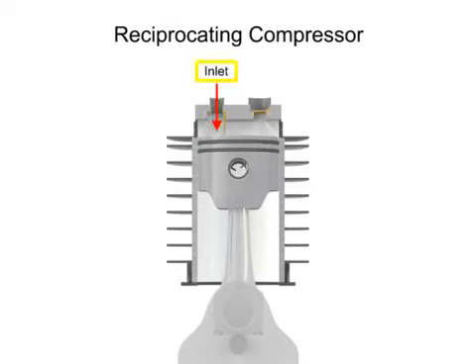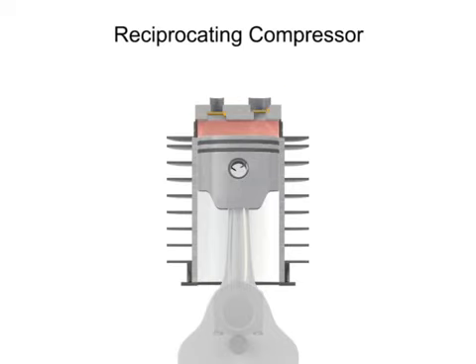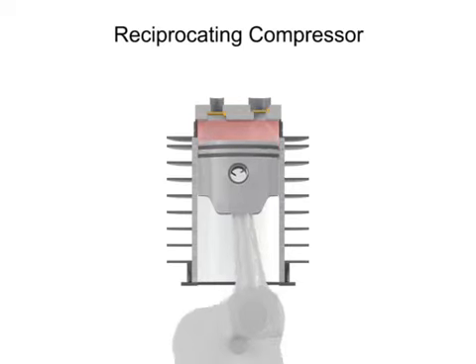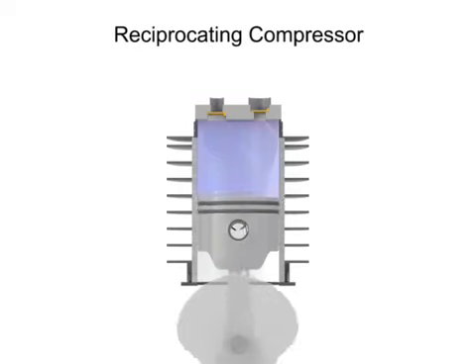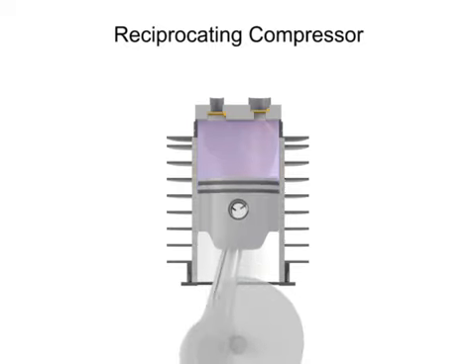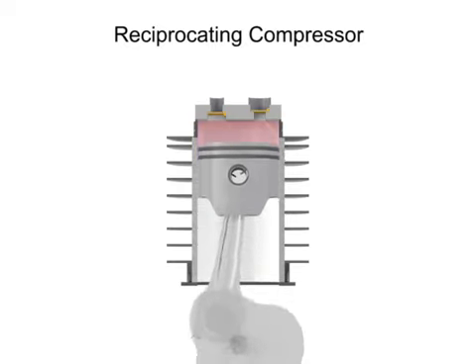The inlet, sometimes called the suction valve, allows atmospheric air to enter the cylinder. The outlet, sometimes called the discharge valve, ejects the newly compressed air from the cylinder. As the crankshaft turns, the piston lowers and raises, changing the available volume within the cylinder.